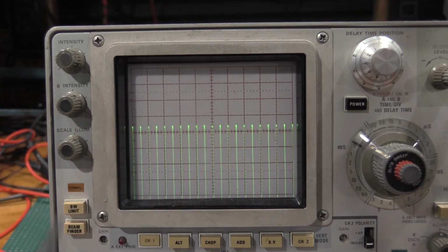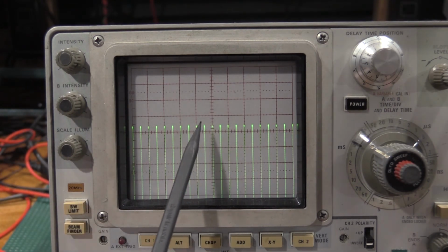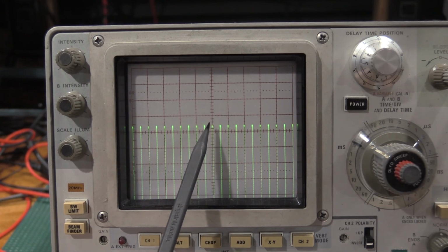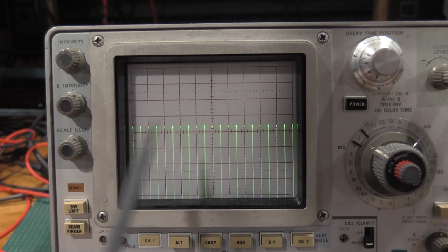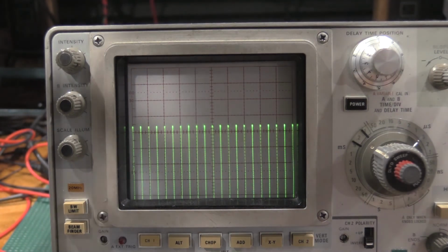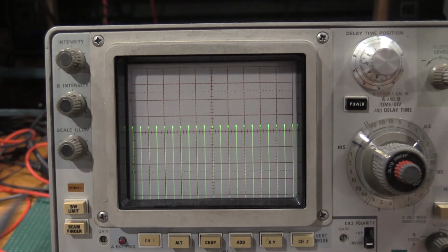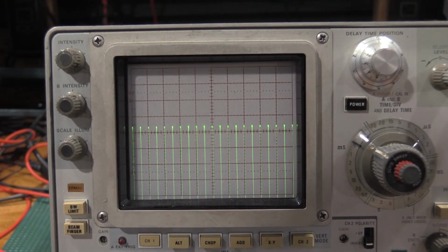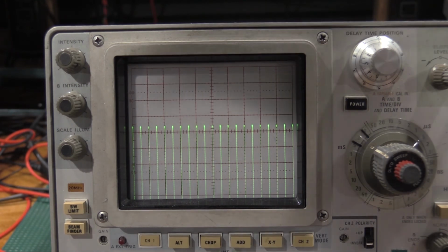Now the important part is this tip is lined up with the center graticule line. If this tip isn't lined up, then you want to adjust the y-axis, which is R1794. So this is a way you can do this adjustment if you don't have a 184 and you can't do the double time markers. This is looking totally okay, no problems. This is very nicely lined up, so I don't need to mess with that one.